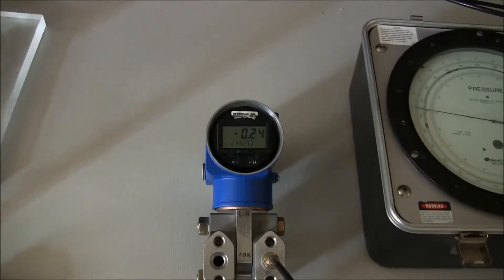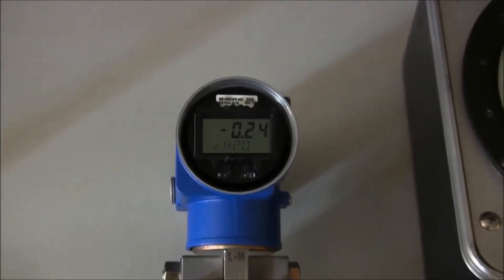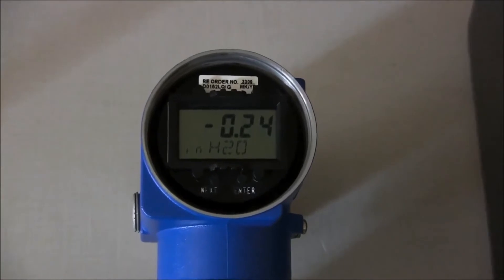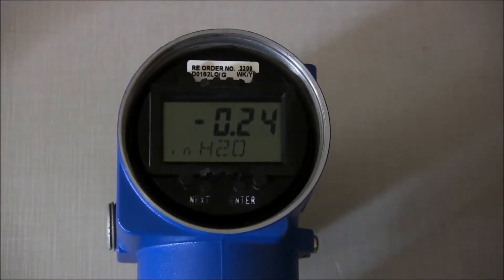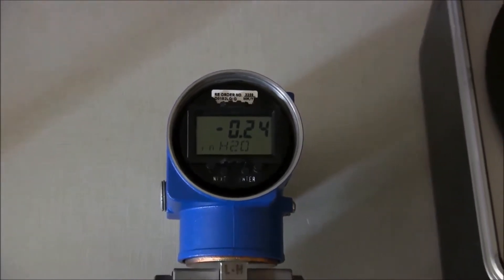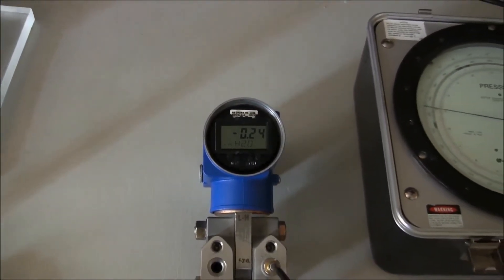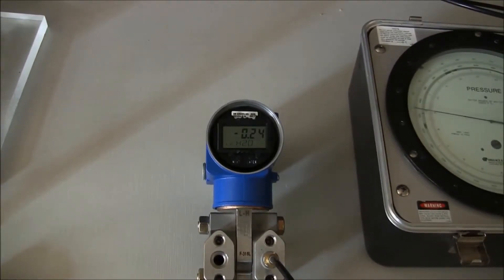The transmitter being used is a model IDP10-T22B21F with a configured range of 0 to 100 inches of water. We will connect our pressure source to the high side of the transmitter and leave the low side vented to atmosphere.